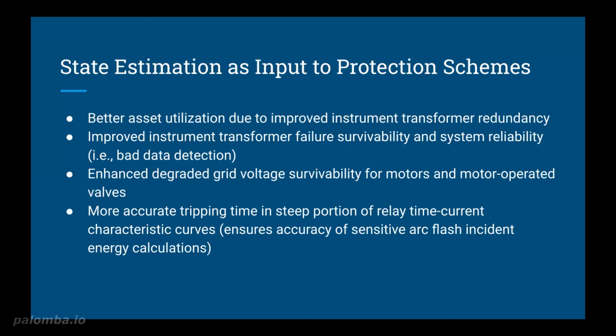Additionally, the state of nuclear equipment could be used as input, such as reactor temperature, allowing the electrical protective system to decide if the motor should die trying to protect the plant, or if it is acceptable to trip the motor offline and protect its internal insulation.